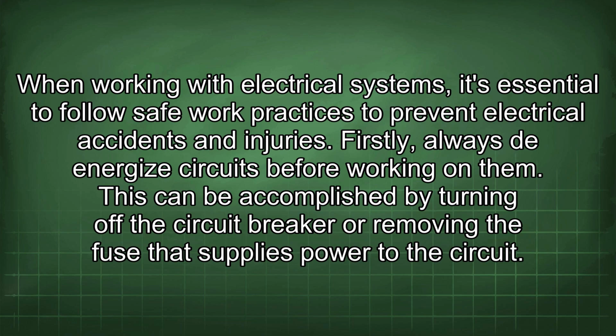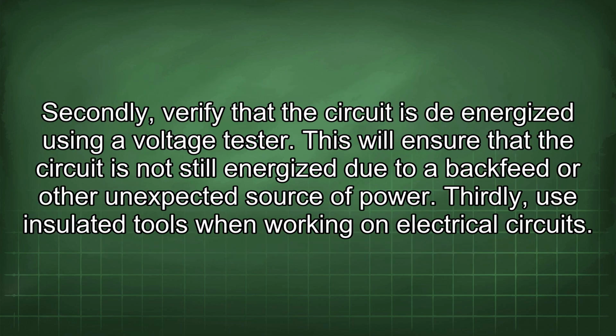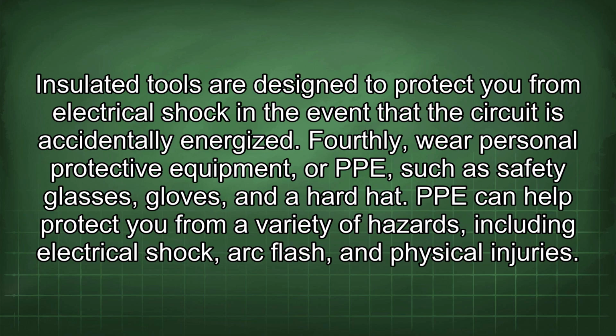Firstly, always de-energize circuits before working on them. This can be accomplished by turning off the circuit breaker or removing the fuse that supplies power to the circuit. Secondly, verify that the circuit is de-energized using a voltage tester. This will ensure that the circuit is not still energized due to a backfeed or other unexpected source of power. Thirdly, use insulated tools when working on electrical circuits. Insulated tools are designed to protect you from electrical shock in the event that the circuit is accidentally energized.